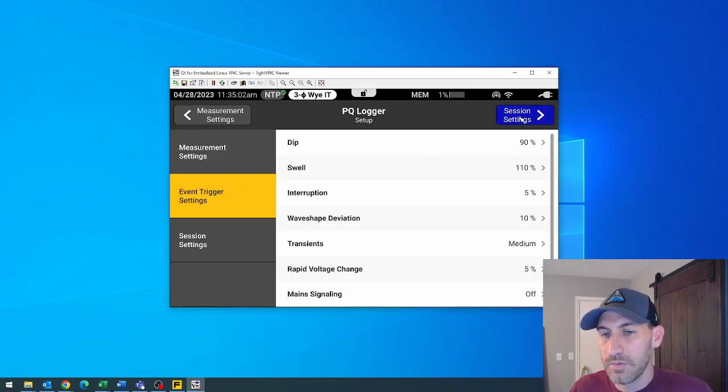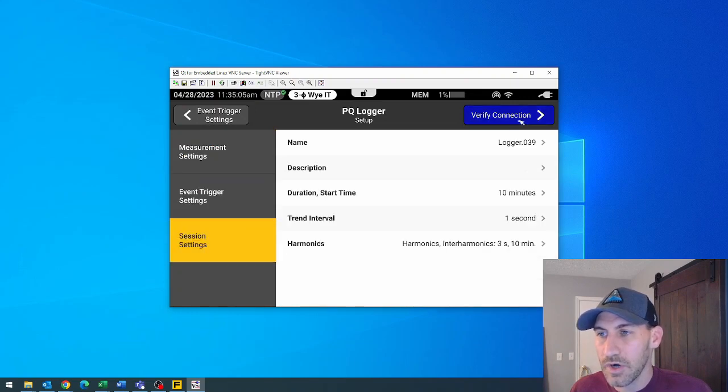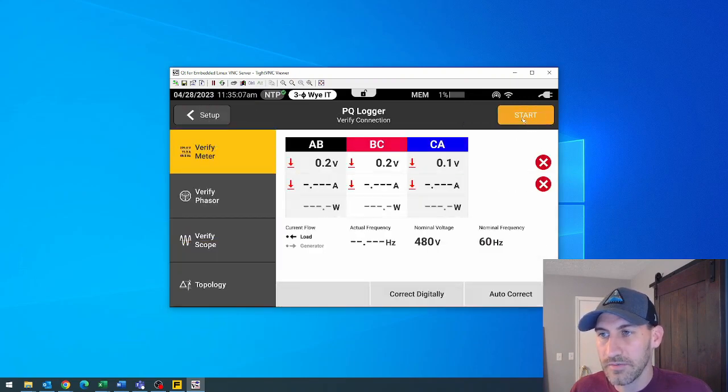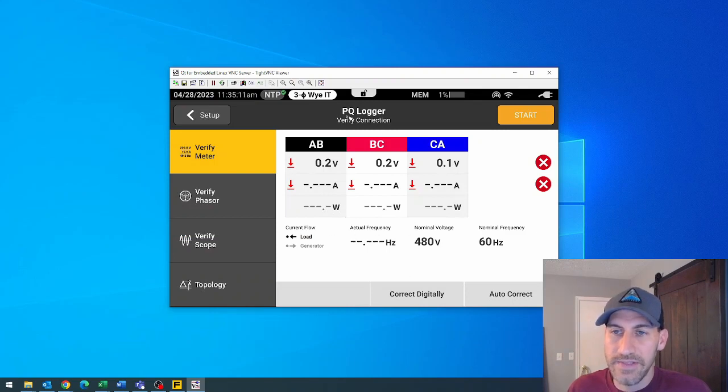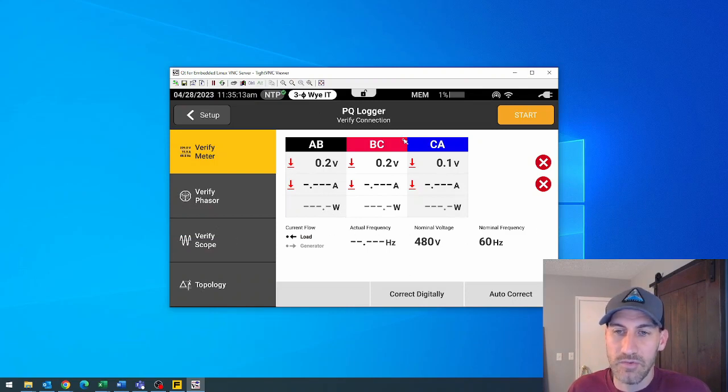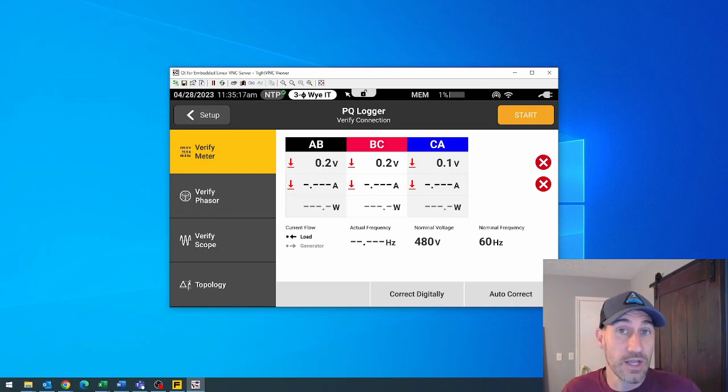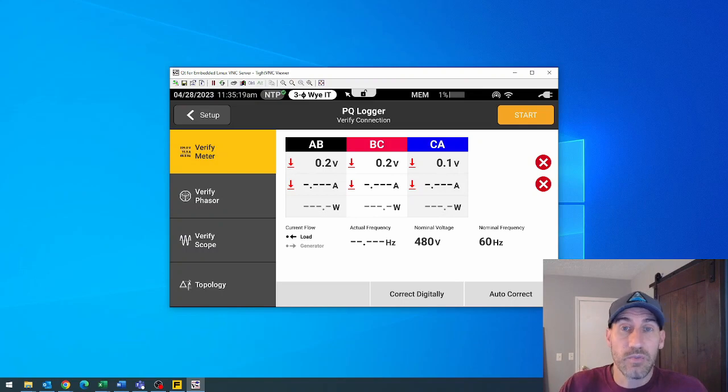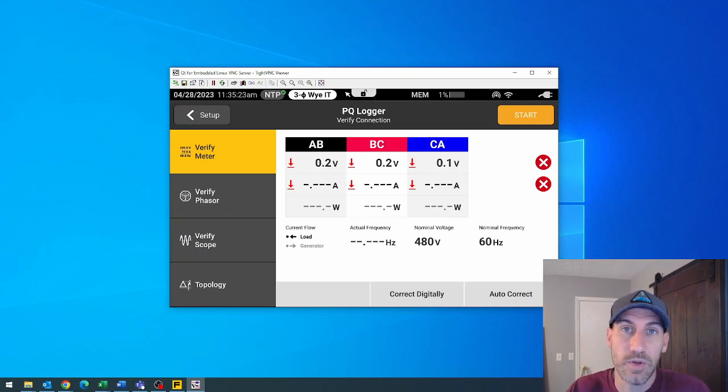And then you could go through and you can even start a logging session right here. Click start log and it'll be off and running. And then you can just disconnect from it, let it run, come back later, download the information just like you did previously with Fluke Energy Analyze Plus and control everything remotely this way.